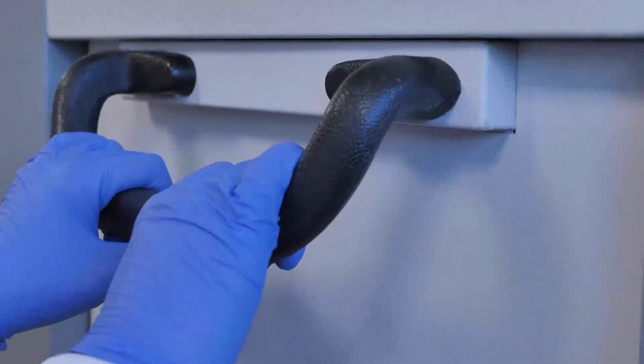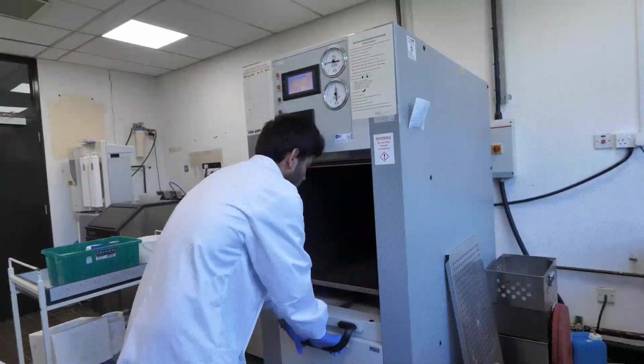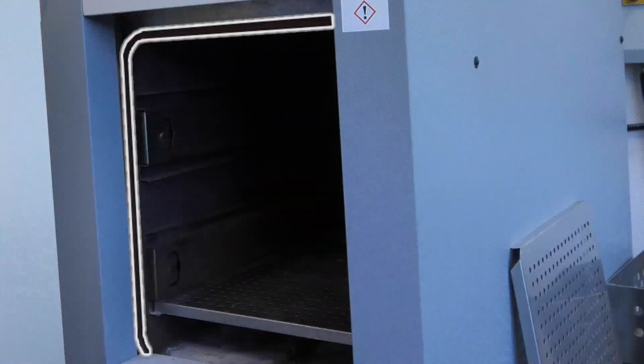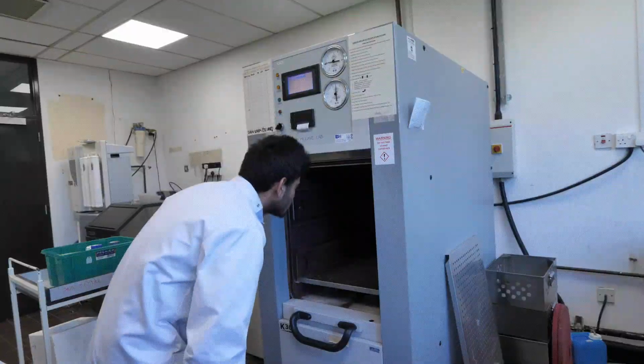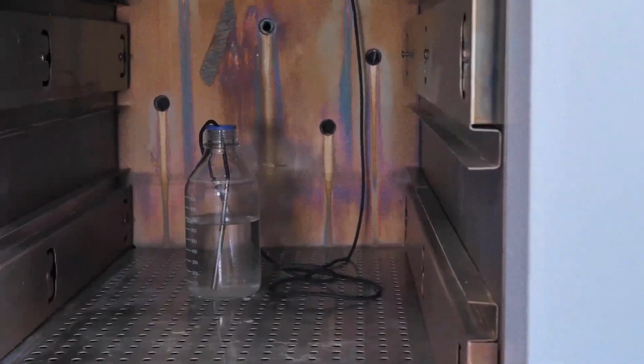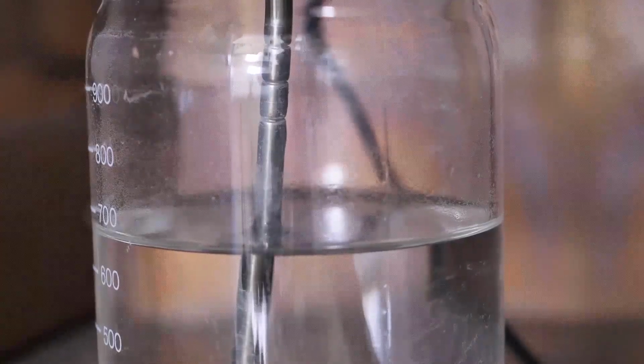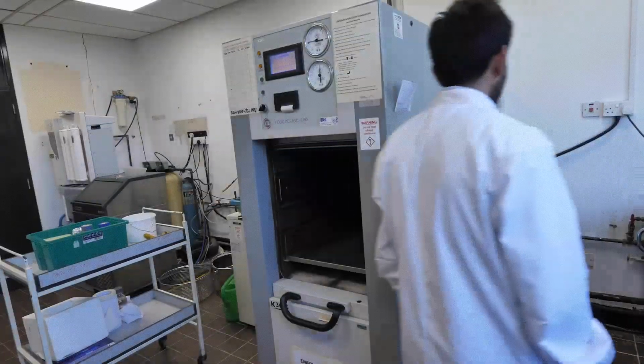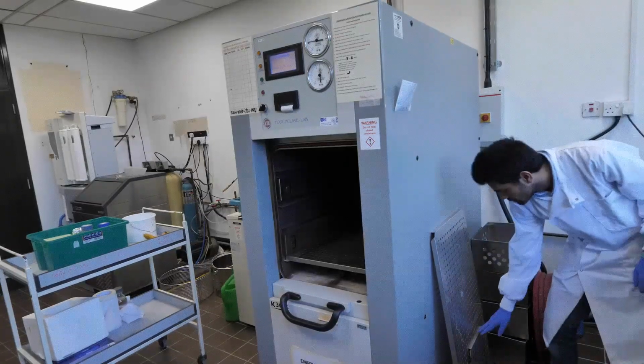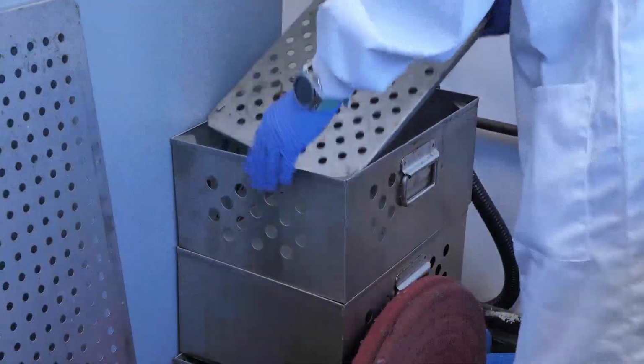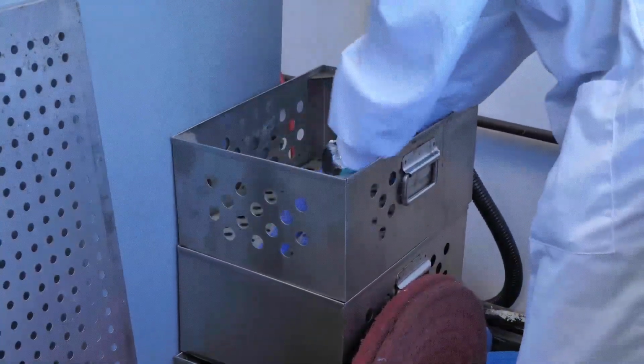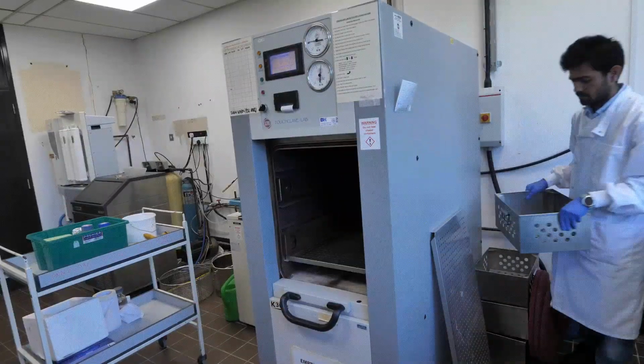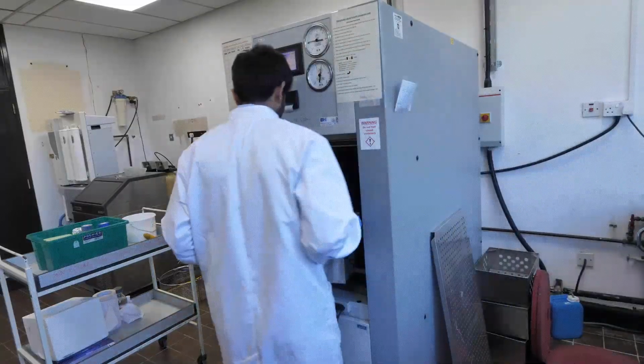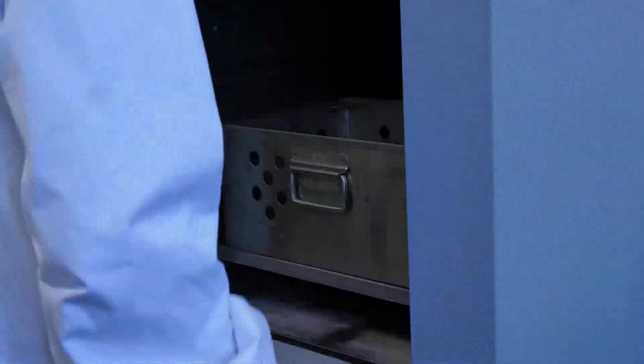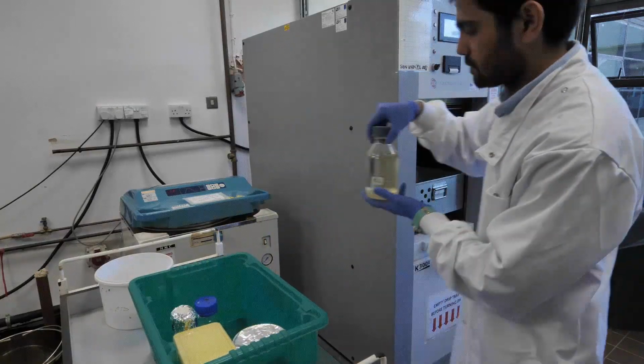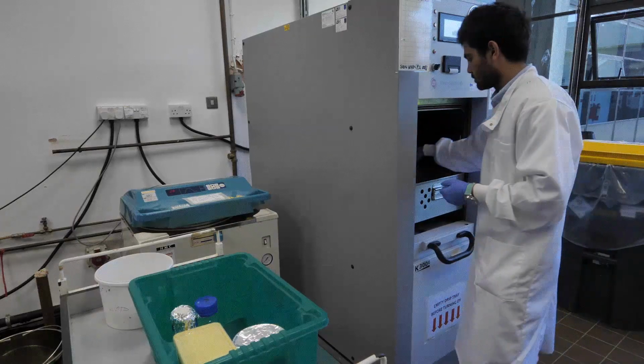Pull down the door to the bottom of the chamber. Check the seal is flush and the interior is clear. Make sure the load probe is inside the bottle. All items must be loaded in the trays provided. Check the bottom plate is in the bottom of the tray for steam circulation. Loosen caps on all bottles and load the trays.